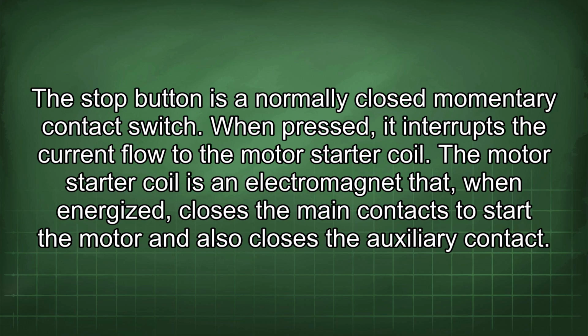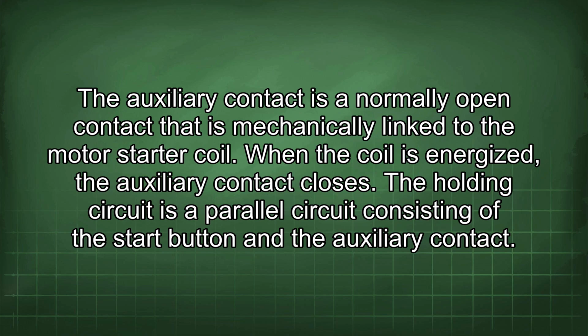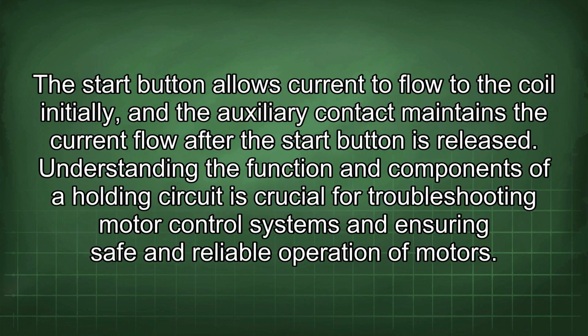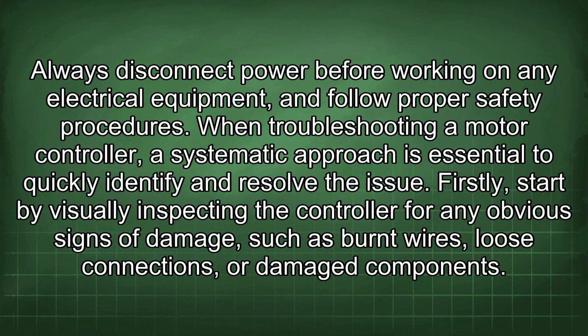The motor starter coil is an electromagnet that, when energized, closes the main contacts to start the motor and also closes the auxiliary contact. The auxiliary contact is a normally open contact that is mechanically linked to the motor starter coil. When the coil is energized, the auxiliary contact closes. The holding circuit is a parallel circuit consisting of the start button and the auxiliary contact. The start button allows current to flow to the coil initially, and the auxiliary contact maintains the current flow after the start button is released. Understanding the function and components of a holding circuit is crucial for troubleshooting motor control systems and ensuring safe and reliable operation of motors. Always disconnect power before working on any electrical equipment, and follow proper safety procedures.